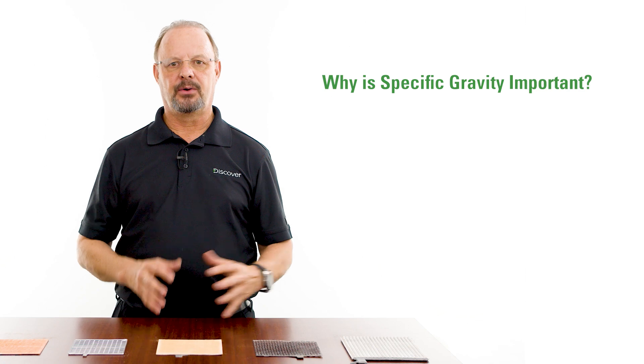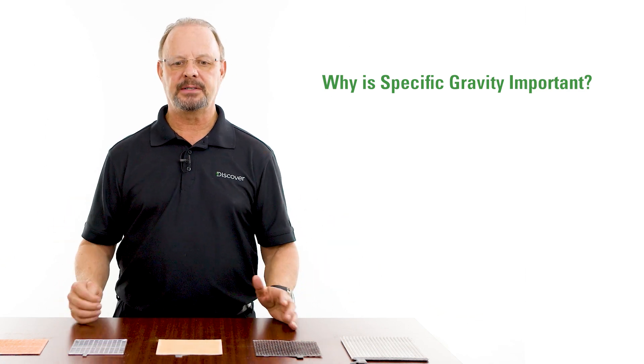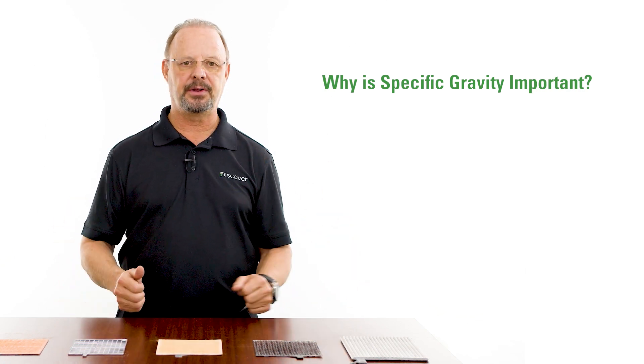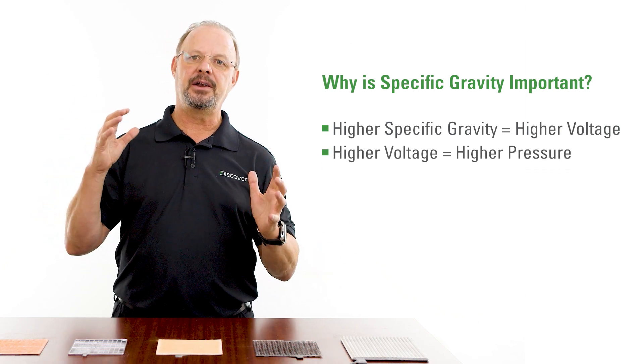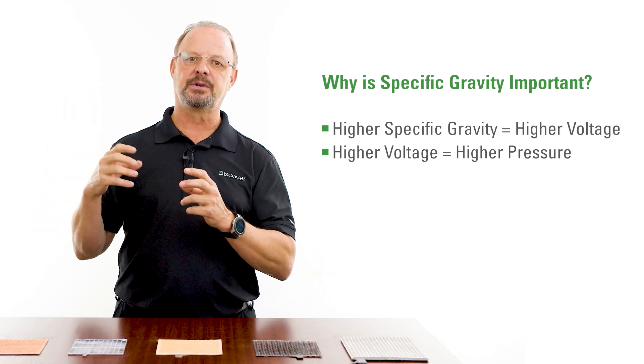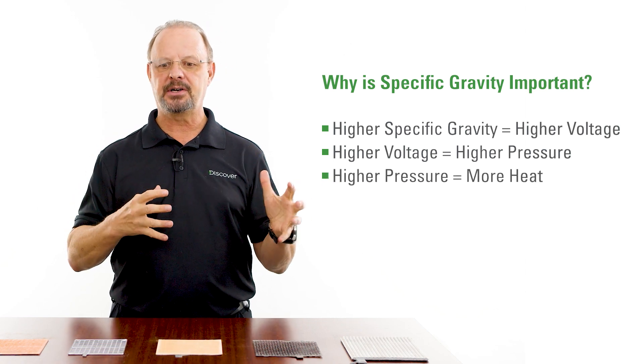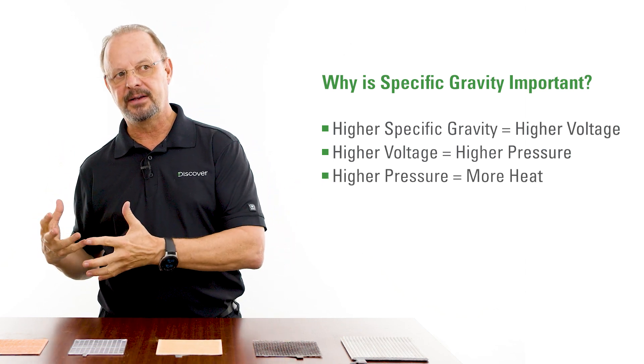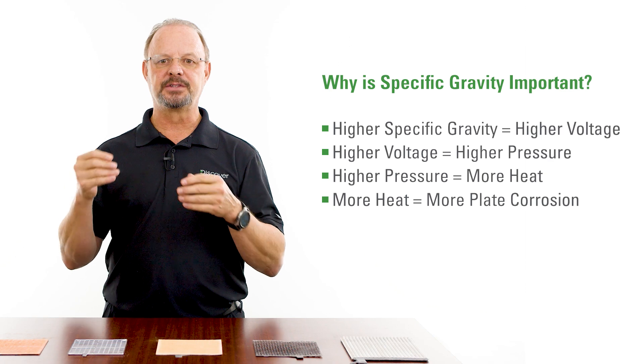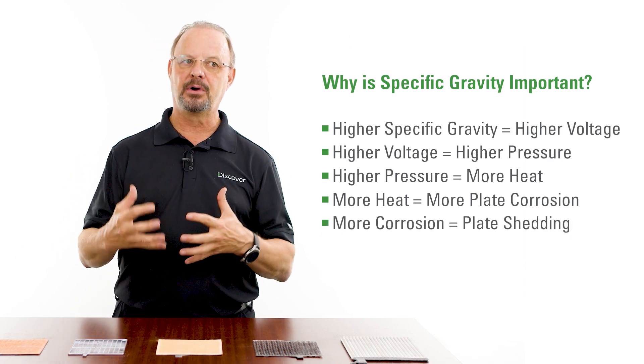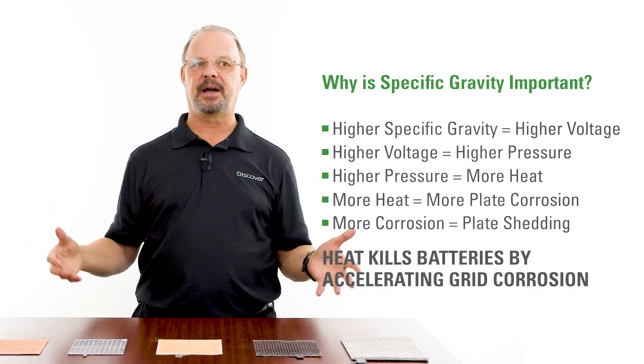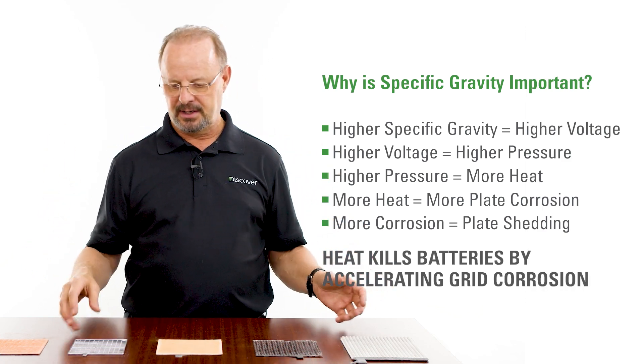So why is specific gravity important? Higher specific gravity leads to higher voltage. Higher voltage equals higher pressure. Higher pressure equals more heat. More heat equals more plate corrosion, and more corrosion equals plate shedding. Essentially, heat kills batteries by accelerating grid corrosion.